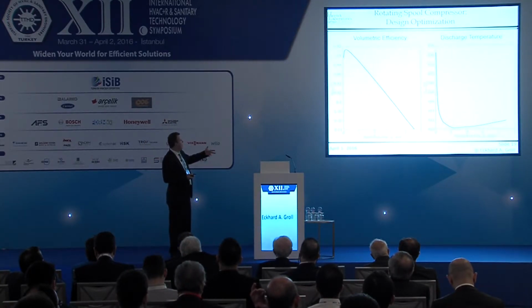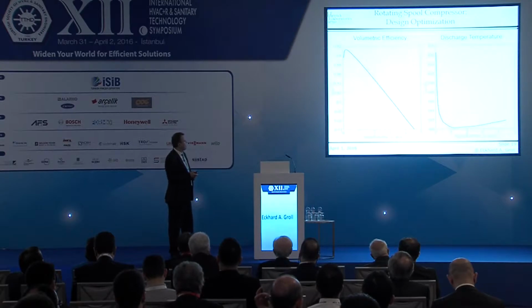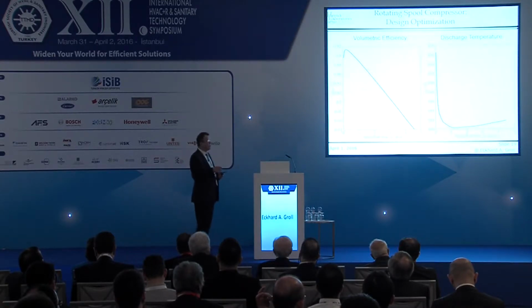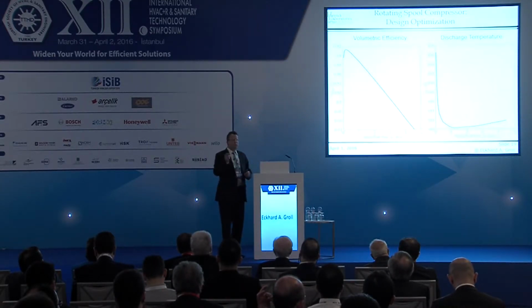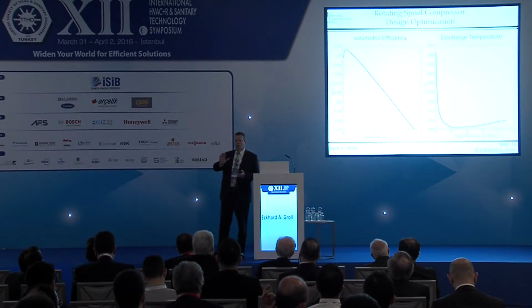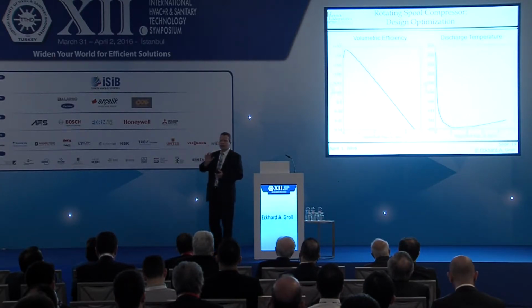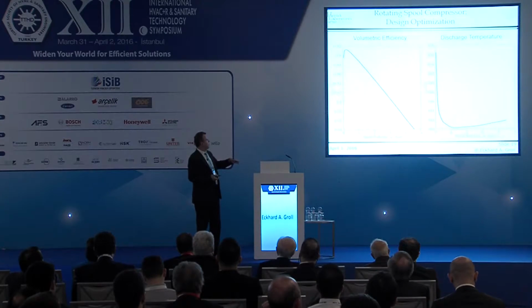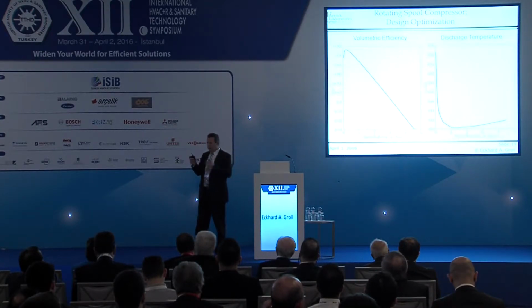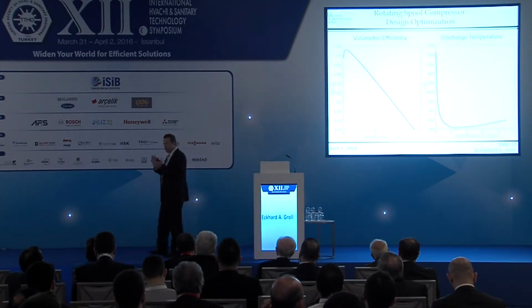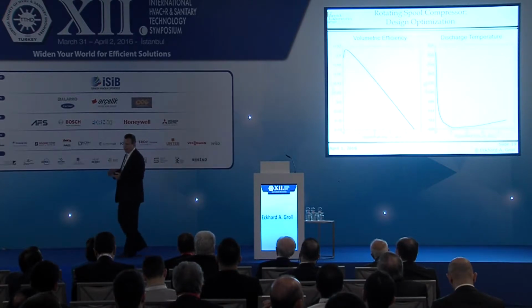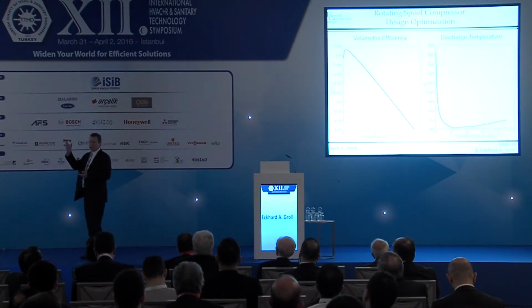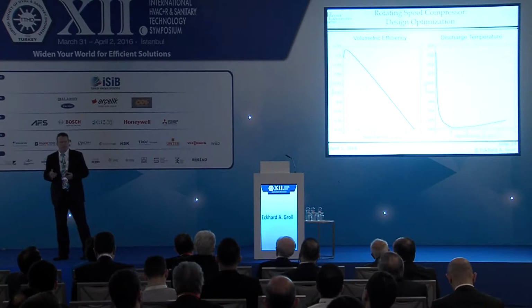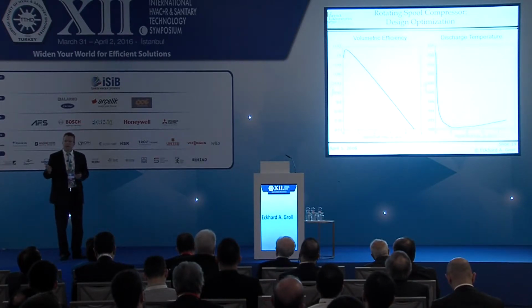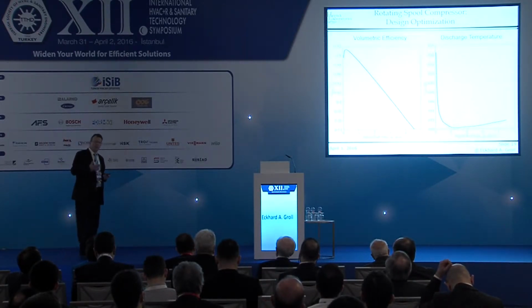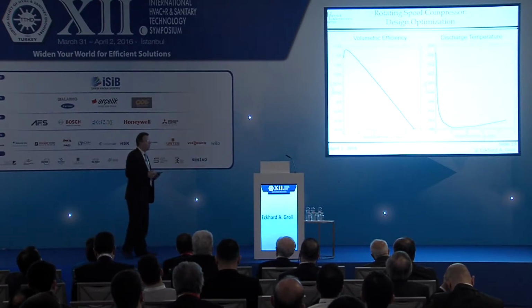Here on the left-hand side, you see, for example, the volumetric efficiency as a function of the spool seal gap, like how close the end plates are rotating against the housing. You see that if you tighten it up, if you reduce the gap, volumetric efficiency goes up. You can achieve over 90%. That's a very good result. But at the same time, the discharge temperature goes up, as shown on the right-hand plot.